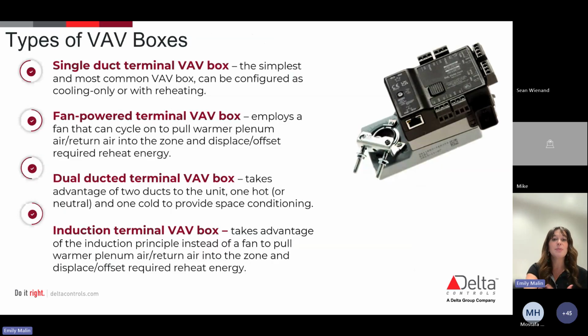A couple of different types of VAV boxes you're going to see. For our purposes, these basically all function the same. Again, we're thinking in the minds of a controller. We want to know what we're controlling, but just so you're aware of what you might see out there. Single duct is probably the simplest and most common, and can be configured, like we said, as cooling only or with reheat. We also have fan-powered and dual duct terminal VAV boxes. Dual duct takes advantage of having 2 ducts, one for hot or neutral, and one for cold.